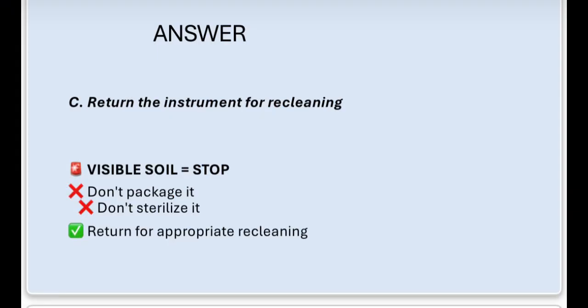Option C is the correct answer. Return the instrument for cleaning. Any visible soil means that the cleaning process was not successful. The instrument must not continue through assembly or sterilization. It must be returned for appropriate re-cleaning according to department procedure.